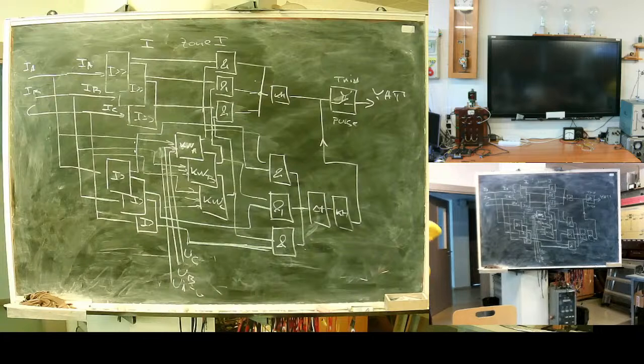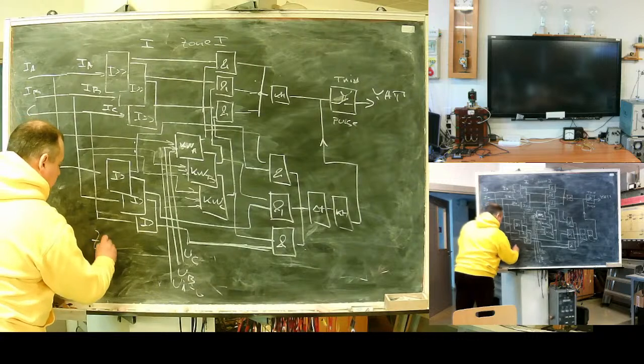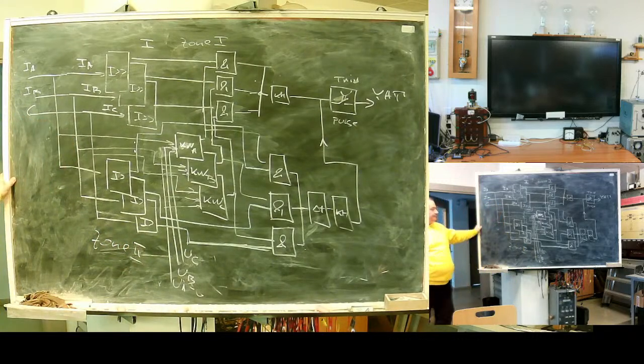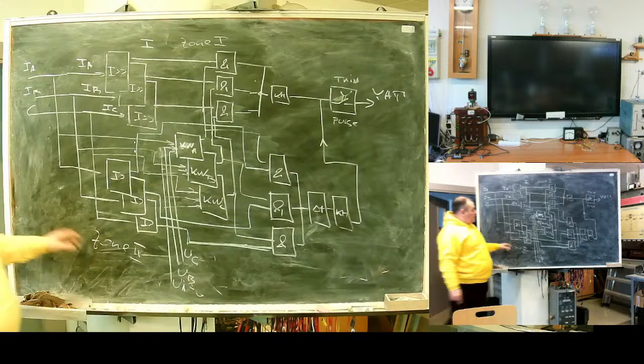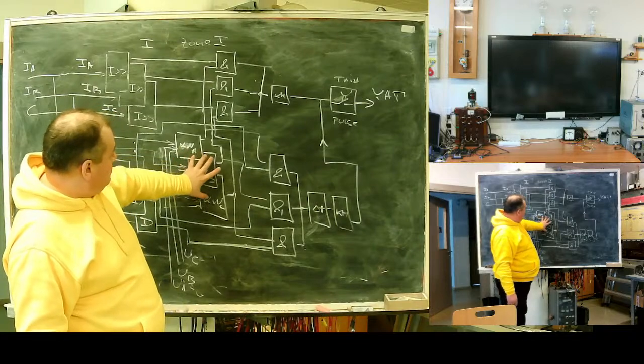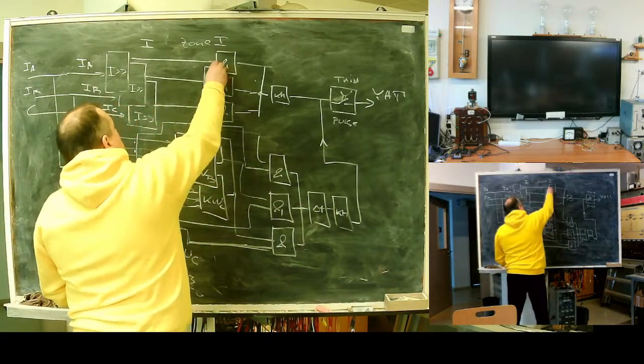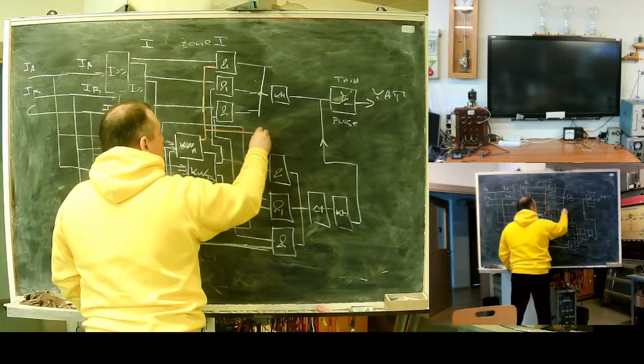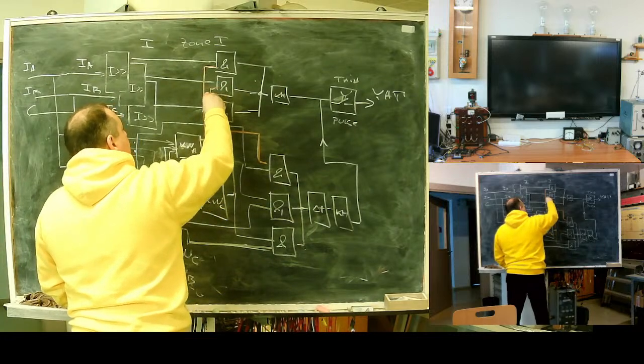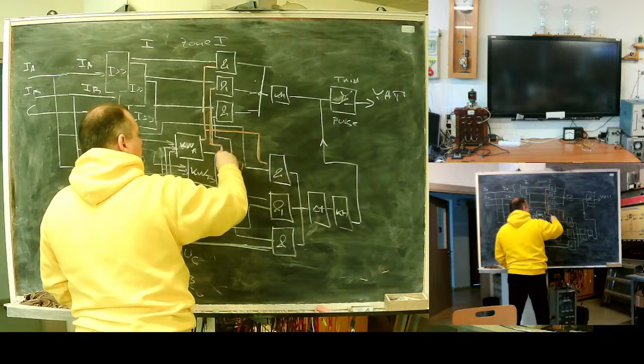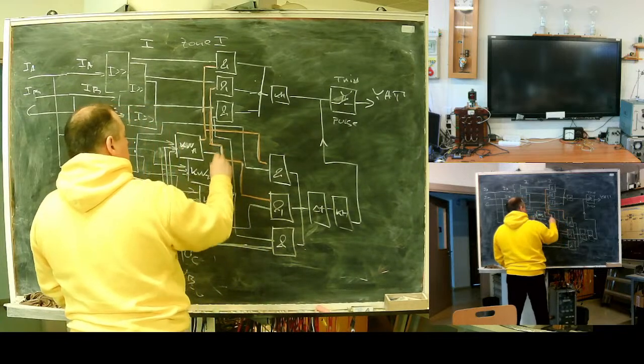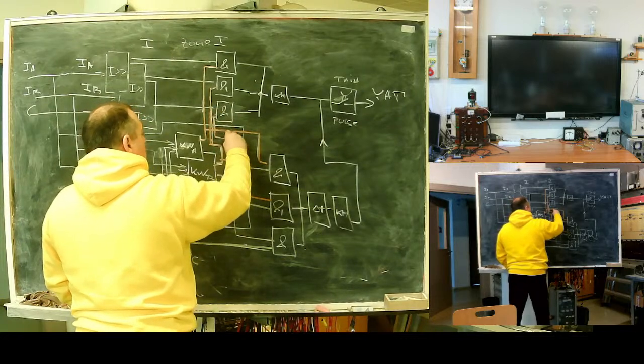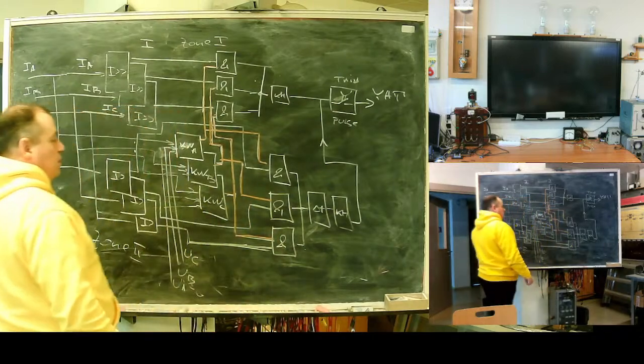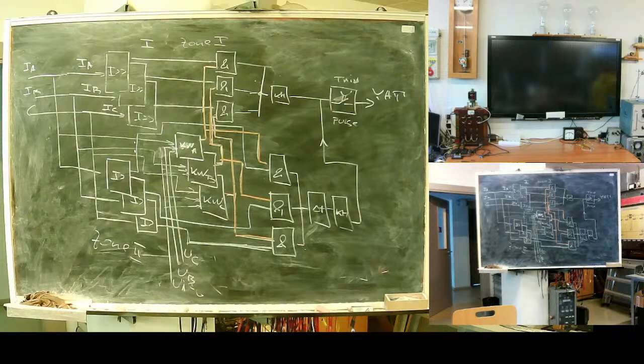Fine. I draw 2 zones protection. One directed instant, and this one directed delay. If you need time-dependent zone, add it. Just extend this line. I showed them in orange. You only will need to extend the orange line to the logic of time-dependent zone.